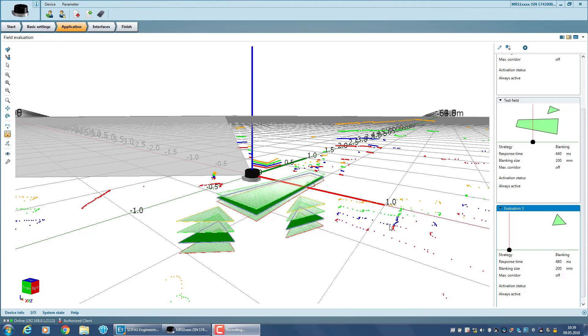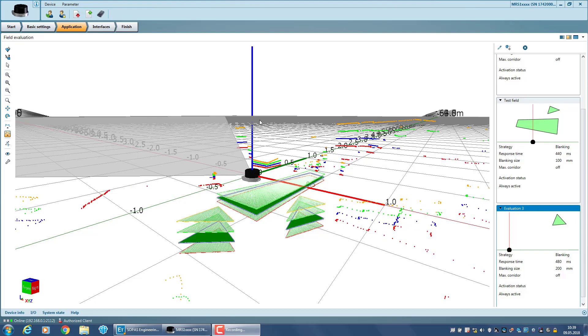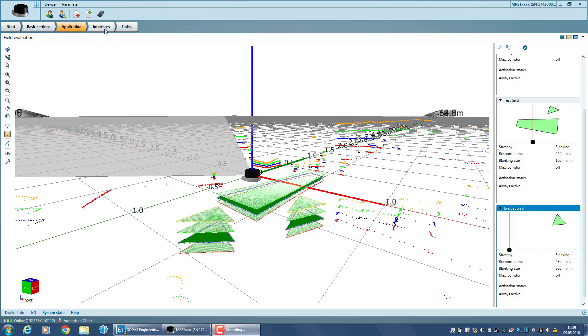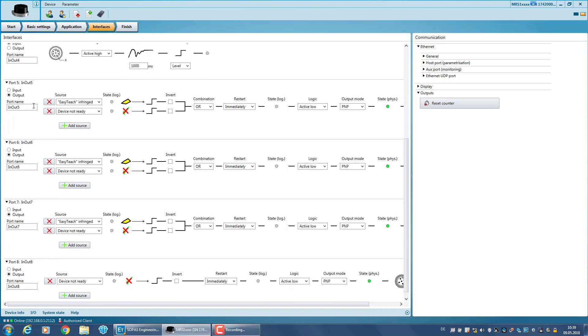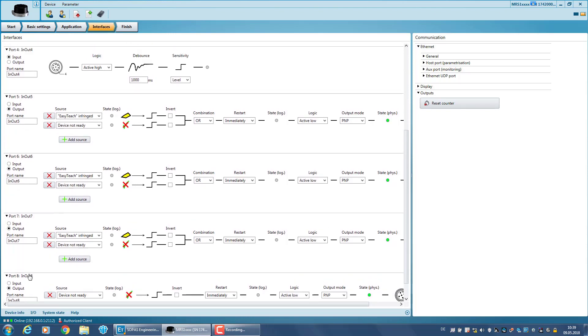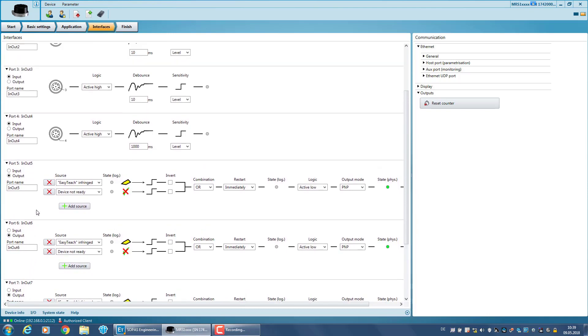The MRS1000 allows for the configuration of up to 8 multifunctional IOs. You can edit these by clicking on the tab Interfaces. Here the definition of each port is defined. The default settings are ports 1 through 4 as inputs and 5 through 8 as outputs. To get a reaction on the evaluation test field we just created, we choose port 5 as an output with the sources DeviceNotReady and TestField.